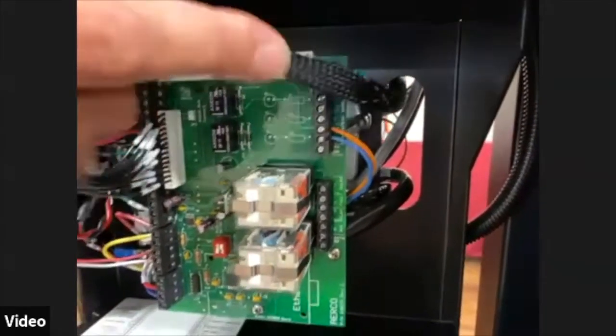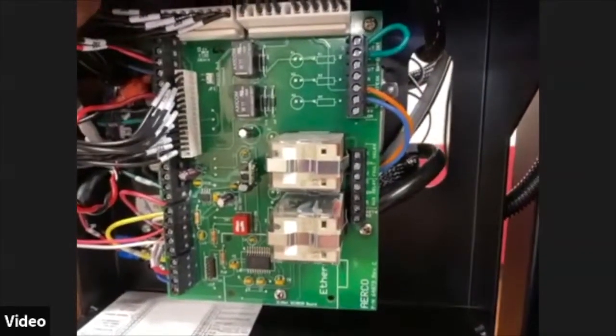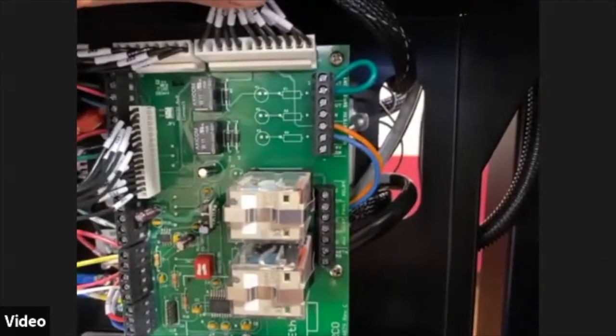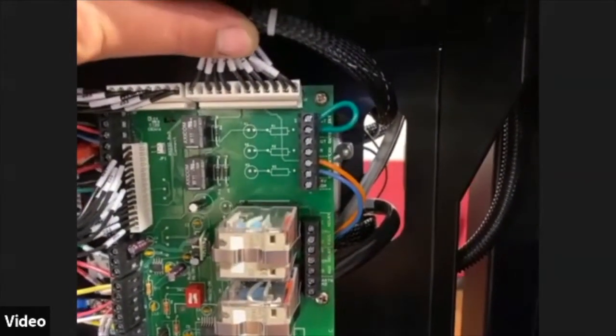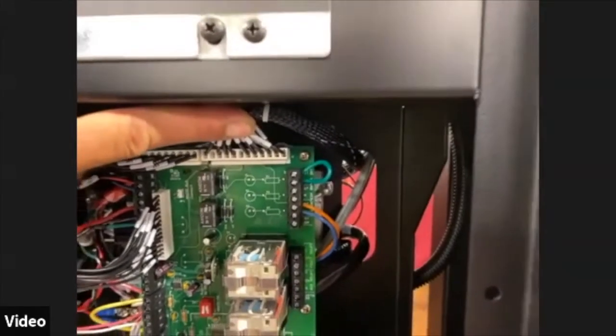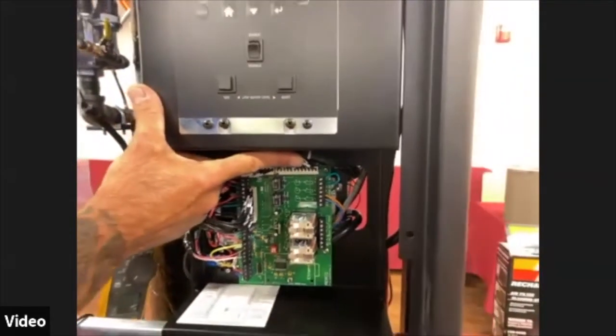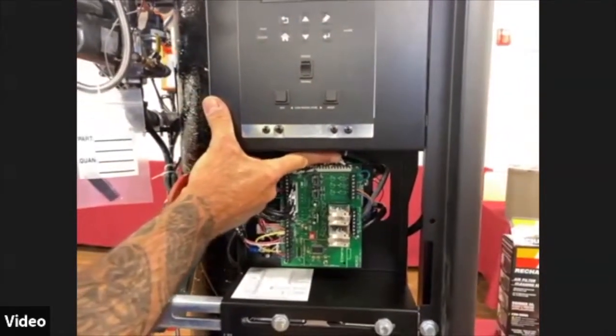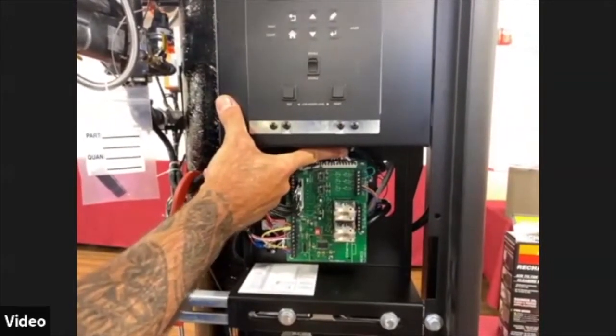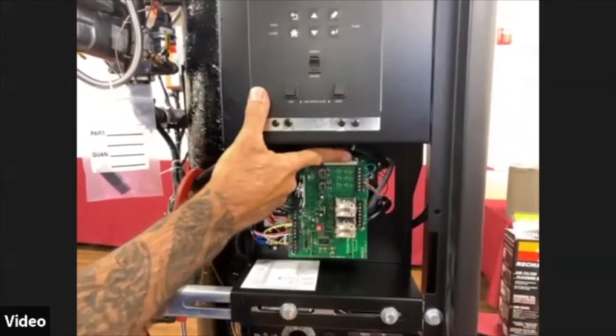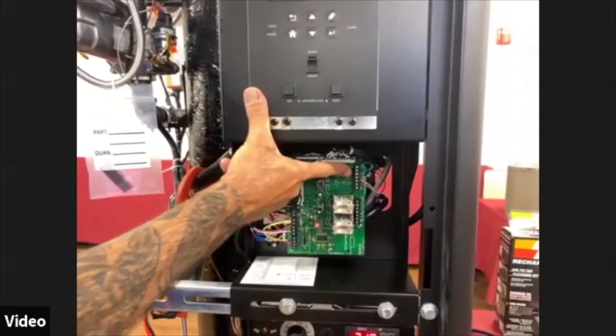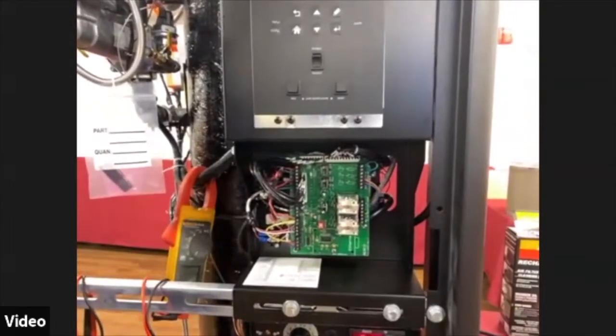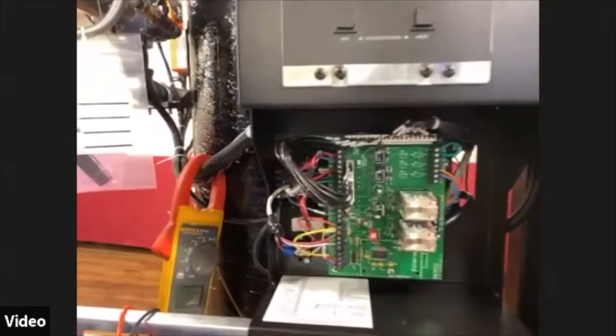And we have our remote enable disable. If you can see this green jumper here, that green jumper right now is in play. Generally that would be where the building management would land their start stop. Please put that through some sort of an isolation relay. This is a powered set of contacts. So if you apply power to those, bad things happen. Boards blow up, burn out.